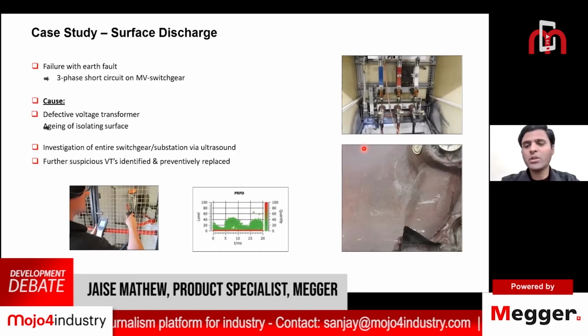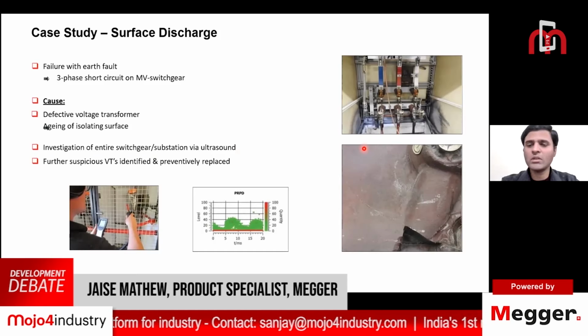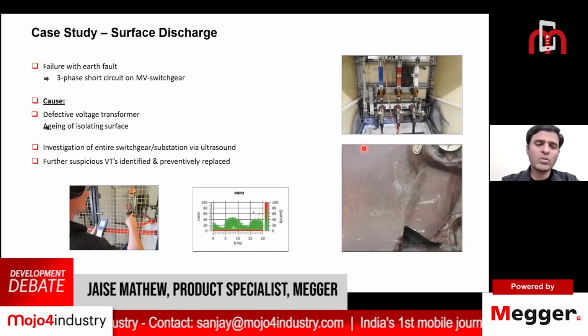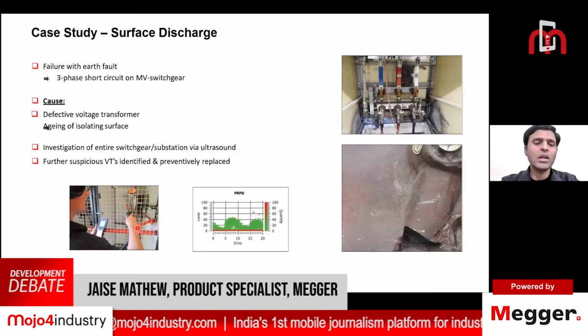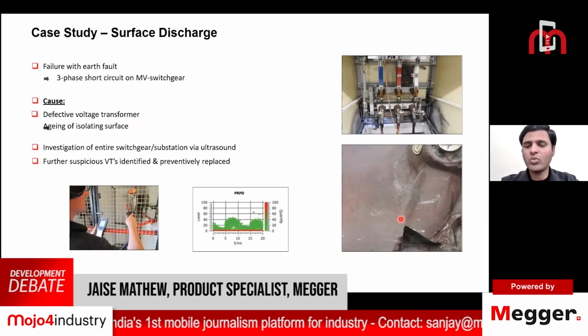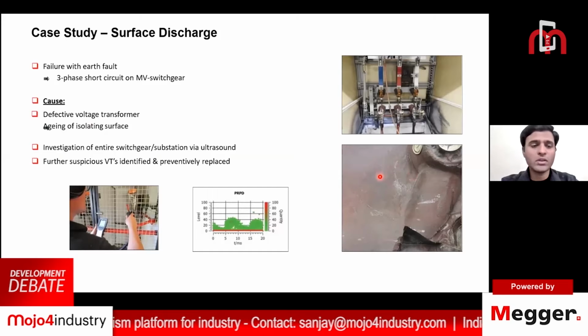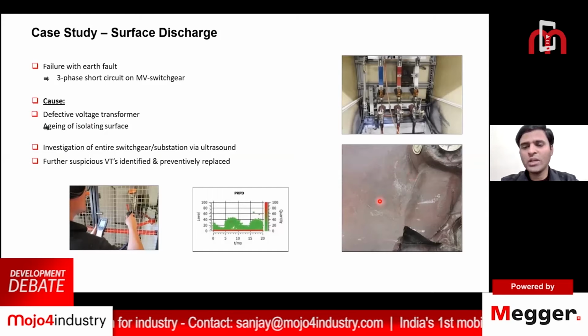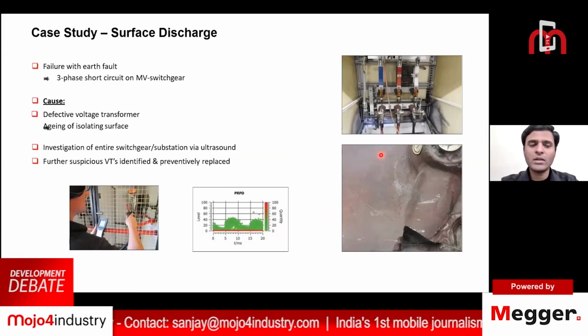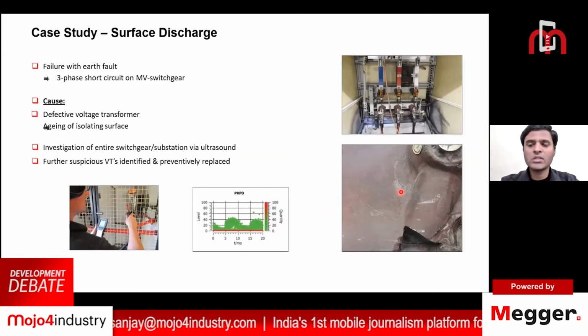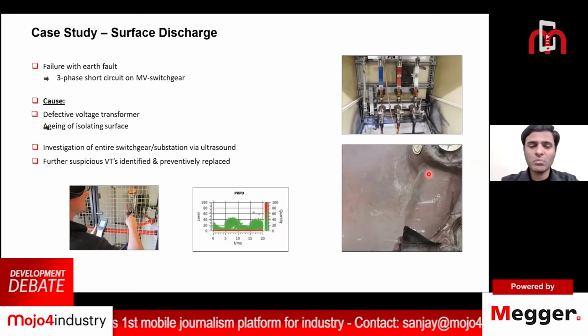This is an online PD measurement on ring main units. There was a failure and they decided to carry out online PD detection. On doing the online PD detection using an acoustic sensor, it was found that there was a defective PT, potential transformer, which had white patches because of the discharges, caused by the aging of the insulating surface. In the complete substation, the investigation was done and the severely damaged or aged VTs or PTs were identified and preventively replaced so that future faults can be avoided.